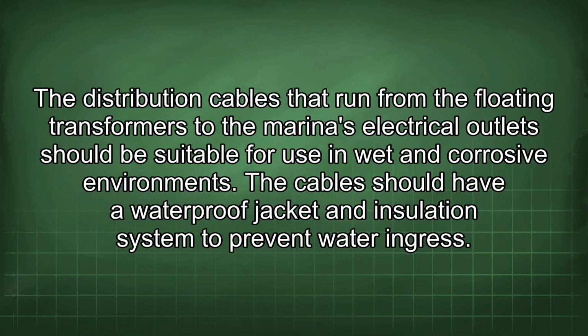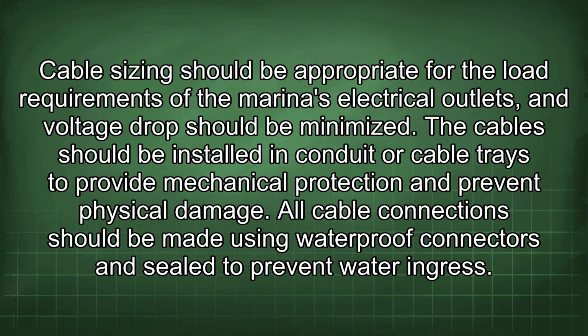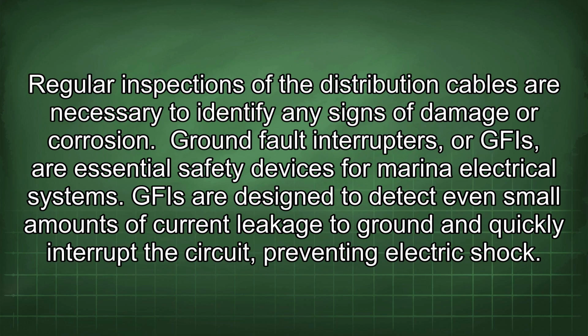The distribution cables that run from the floating transformers to the marina's electrical outlet should be suitable for use in wet and corrosive environments. The cable should have a waterproof jacket and insulation system to prevent water ingress. Cable sizing should be appropriate for the load requirements of the marina's electrical outlets, and voltage drop should be minimized. The cable should be installed in conduit or cable trays to provide mechanical protection and prevent physical damage. All cable connections should be made using waterproof connectors and sealed to prevent water ingress. Regular inspections of the distribution cables are necessary to identify any signs of damage or corrosion.